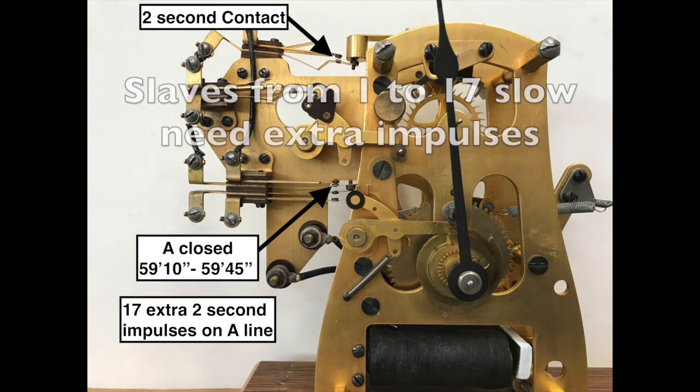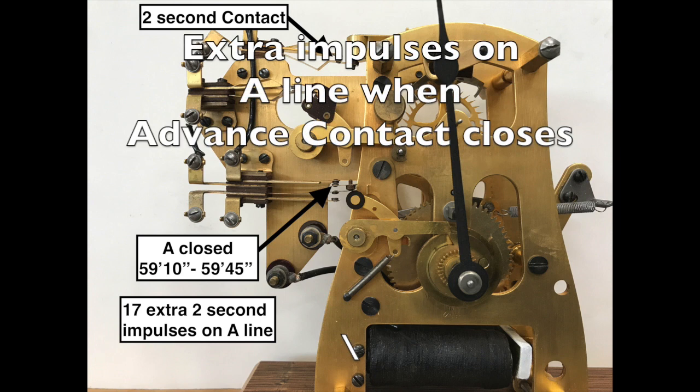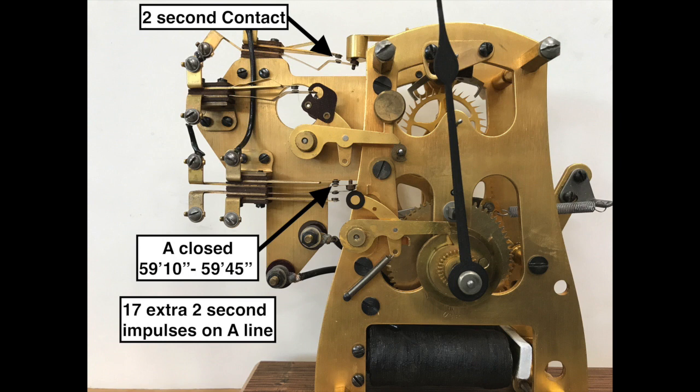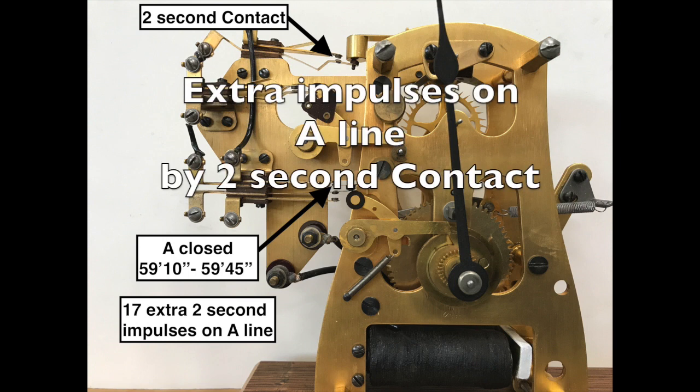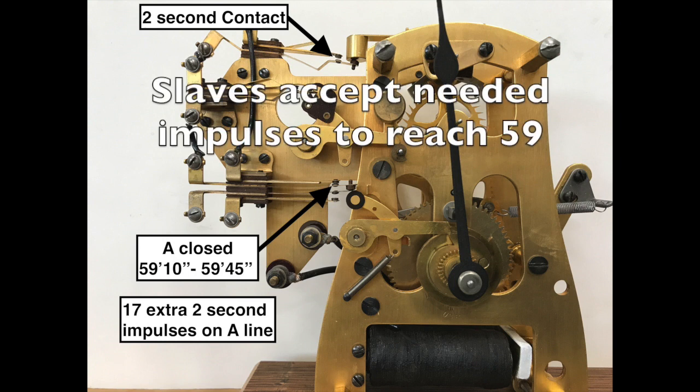Slave clocks that are from 1 to 17 minutes slow can be corrected with extra impulses on the A line when the advance contact closes. The advance contact is active between 59.10 and 59.45. The extra impulses are generated by the 2 second contact. The slaves accept as many 2 second impulses as needed to reach the 59th minute.